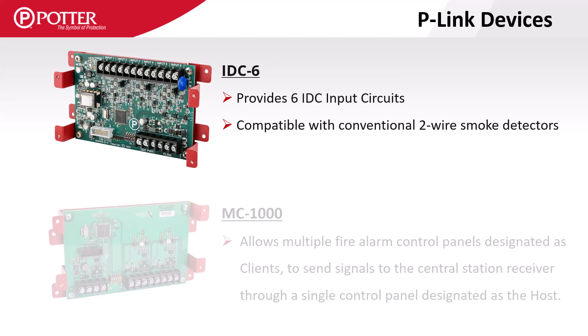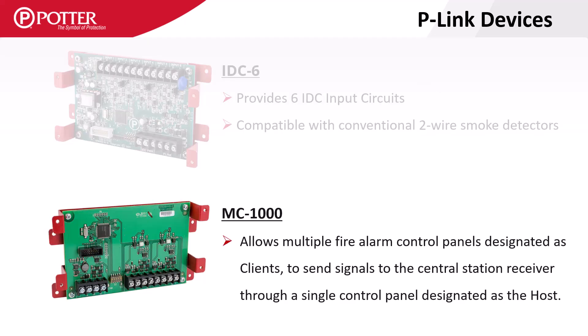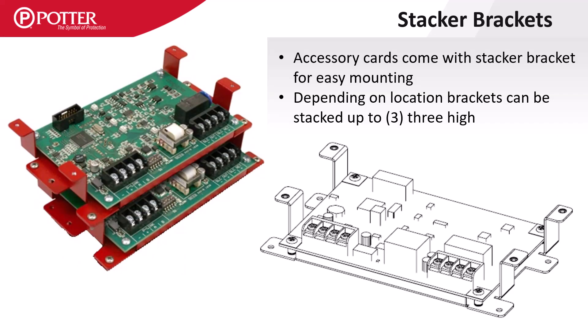The IDC-6 card provides a control panel with the ability to monitor six separate two-wire conventional smoke detector circuits. The MC-1000 allows one host control panel to report to the central station for up to 62 client panels. The stacker bracket mount saves space inside an enclosure by allowing the modules to easily stack on one another.